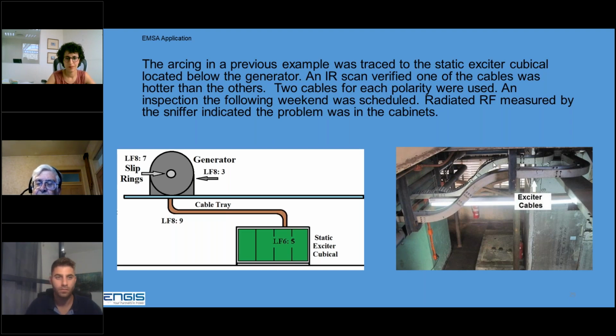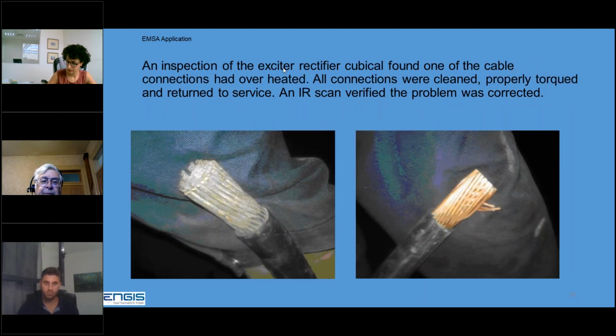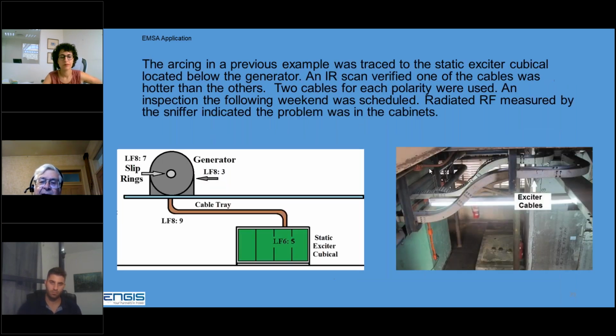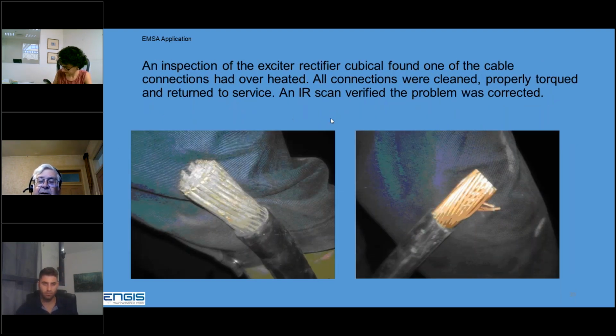Here's that cubicle. Here are the cables going up to the slip rings. There's 2 conductors in each one of these cable trays. And they did an infrared scan and they found out that one of the cables was very warm. The other 3 were not. So they took an outage that weekend to find out what was happening. And when they opened up the exciter rectifier cubicle, they found one cable connection had overheated. It had not been torqued properly. So all the connections were cleaned, connections properly torqued, returned to service. They did an infrared scan, and now all 4 cables were the same temperature. So they had found the problem of one bad conductor and they corrected it.